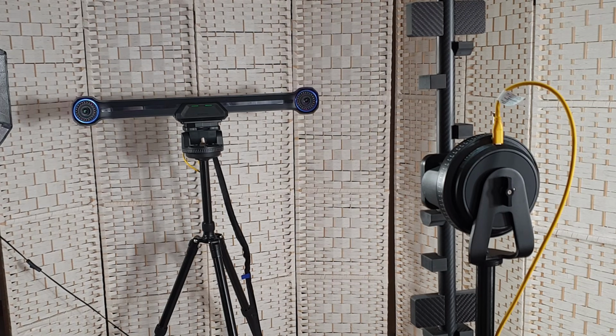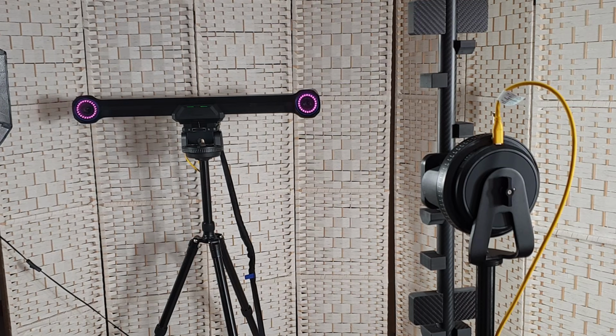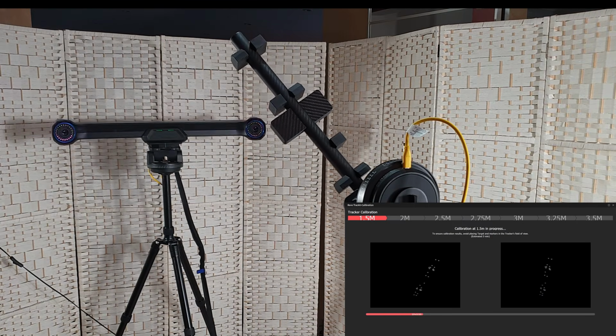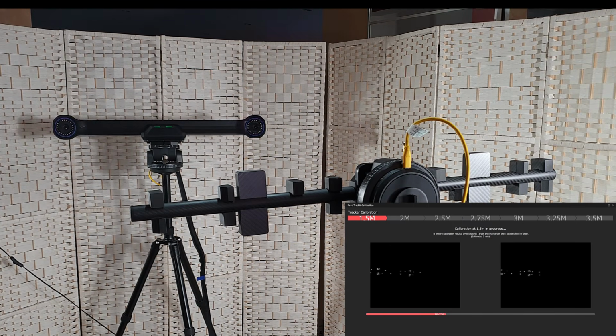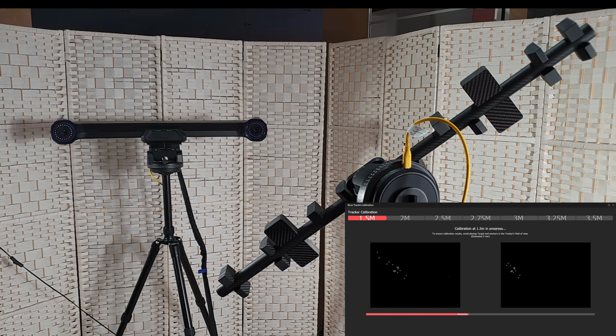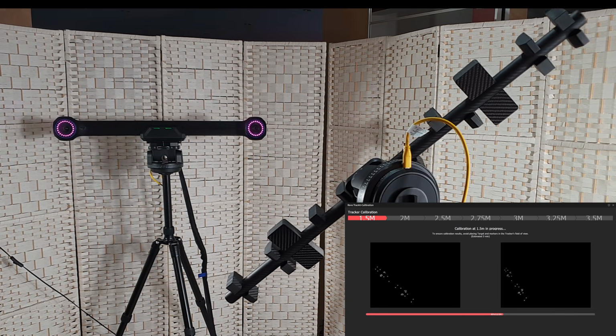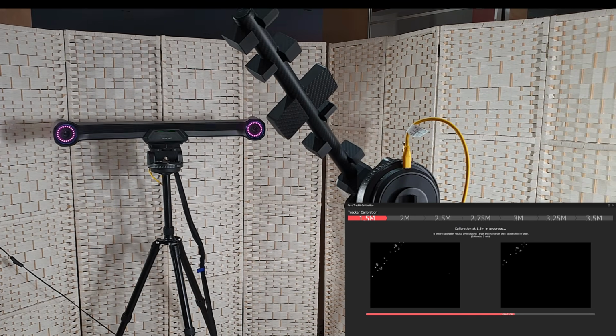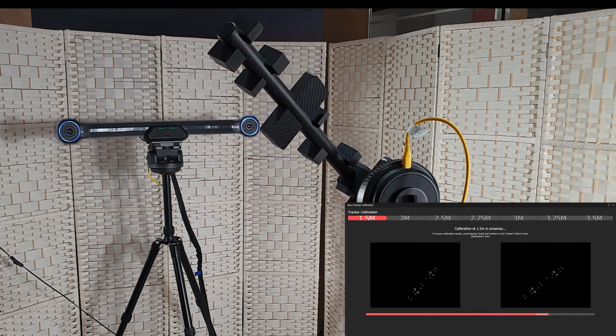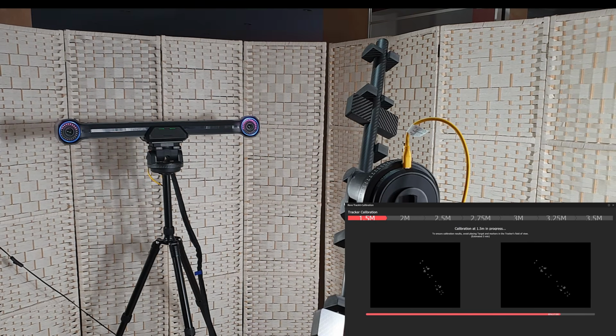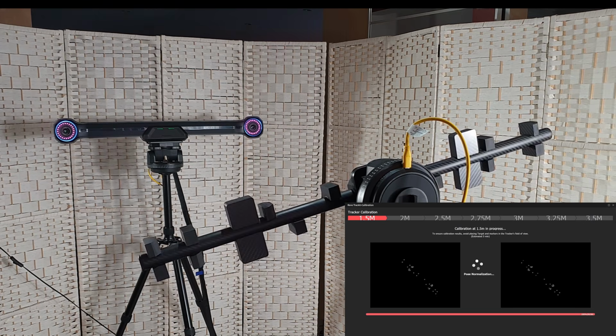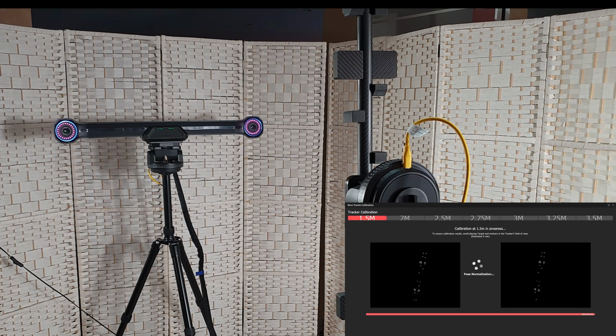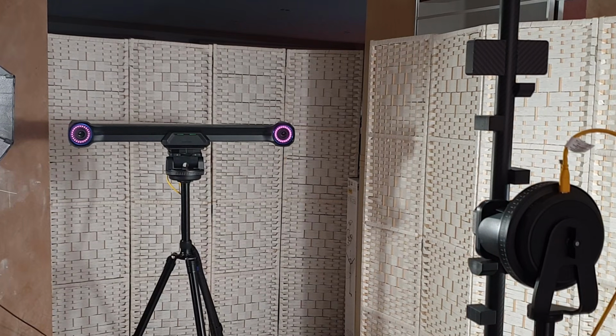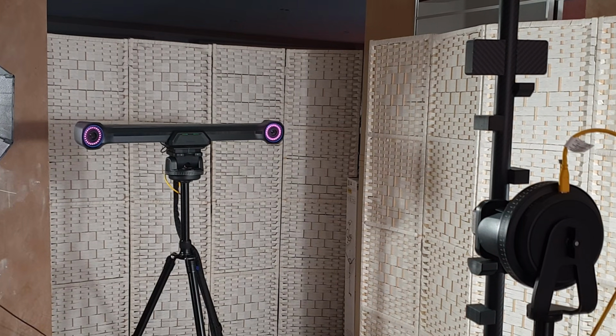Here we can finally see the scanner start to move during the automatic calibration, using the 2-axis gimbals to precisely position the camera bar as well as the calibration bar to calibrate the camera's field of view as well as depth. This is by far the longest part of the calibration. There are a total of 7 steps, so it takes around 30 minutes to complete. You can just set up the calibration process and go do something while it does its thing. And every so often you just have to reposition the camera bar a bit further away from the calibration bar and continue the calibration.